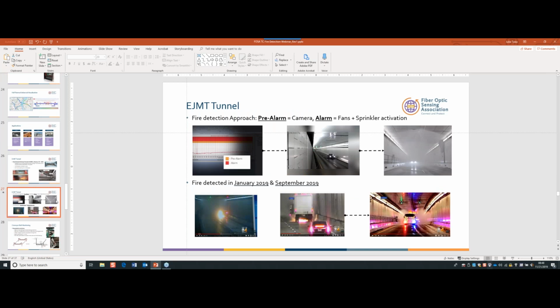This slide pretty much depicts the beauty about the system. We have up to 106 relay outputs that can connect each one of those zones. We can go even beyond that. So in this similar project, we had at least 200 plus zones where the relay output can tie into the fire panel and activate not only the extinguishing system, the suppression system, for that particular zone, which is amazing. We can pinpoint within a meter which zone to activate. So you're saving water, you're saving foam, you're saving everything. And in this case, it's more water. The second approach is you can also have a pre-alarm to activate a camera. And that was the exciting thing about this project, the integration is so simple and so seamless, and we are not tied into any other systems. We are very flexible to make sure that the goal of extinguishing, the goal of suppression, is done in such an easy way.